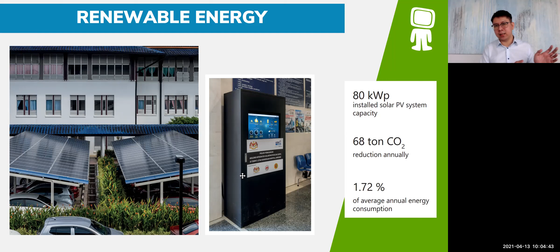On the indoor environmental quality or indoor air quality, this hospital is multi-level, multi-story. So all the critical rooms were installed on the upper level where it is nearer to the AHU unit, where you require less ducting, and also less pressure loss. So in this case, the fresh air was brought into the AHU on the higher level, and it was going down to the space, and some of the lower level was air conditioned as well, by getting the chilled water from the air cooled chiller, and some areas are running on FCU, and also getting the fresh air from the outside into those FCU.